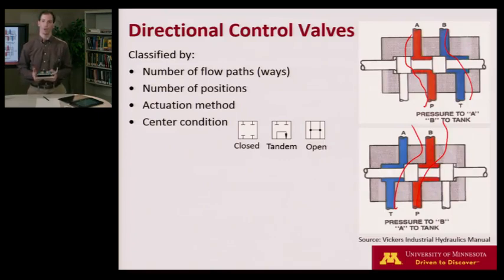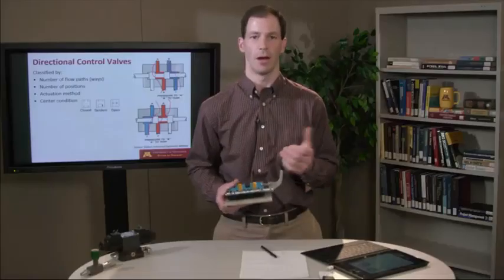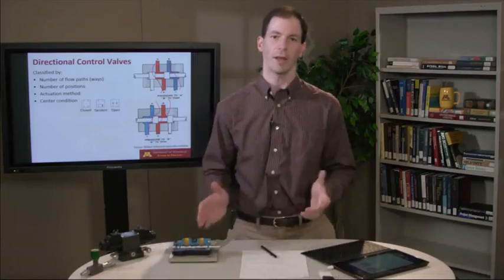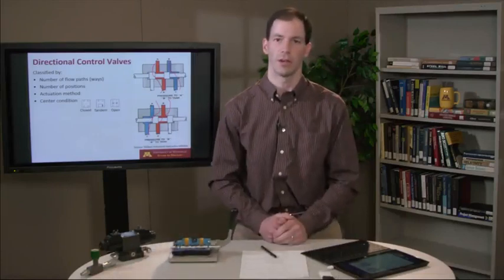Then we talk about actuation methods. This would be a manually actuated valve with a lever. There are lots of different manual actuations. We also have solenoid actuated valves. We often have a spring return, such as this valve that has a spring right here that's returning the valve. We can have hydraulic pilots, pneumatic pilots, lots of different ways to drive valves.